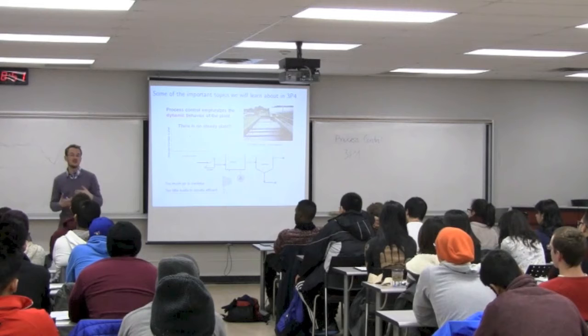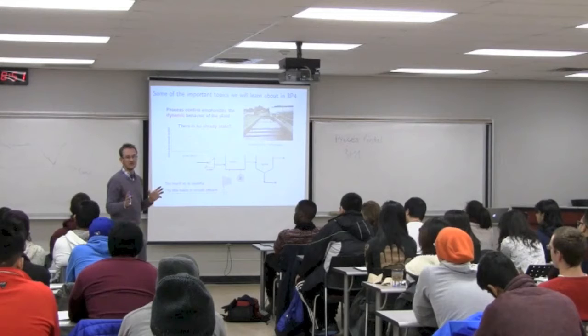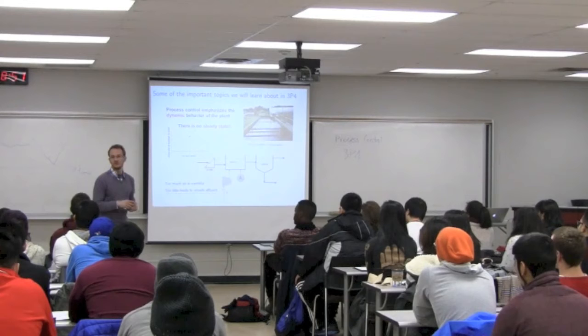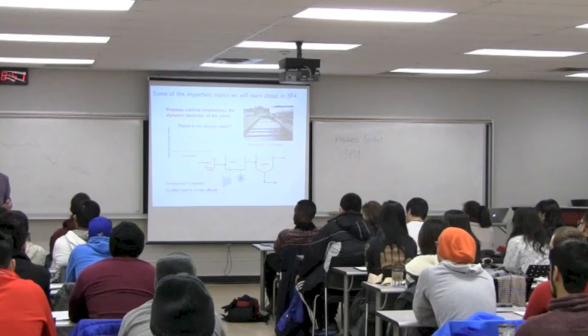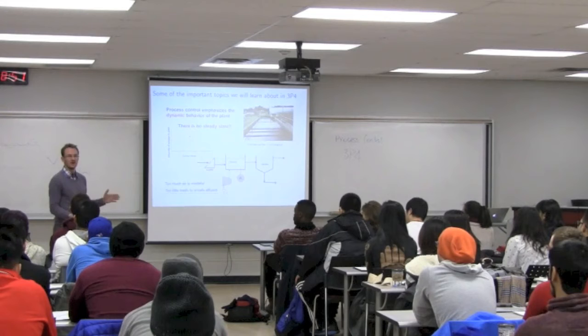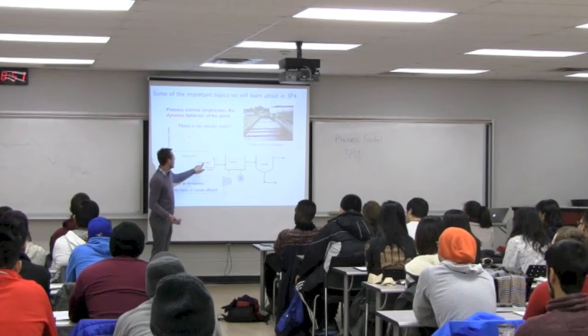Now, obviously, then there's design on how big that vessel should be. There's some engineering work done to design the capacity for that vessel, and they'll design it for most treatment flows. But then a storm comes, and you get a high volume of wastewater coming in because our sewer systems are not separated. Wastewater and water overflow from the roads and snow melting often get combined. So when you get a big ice melt or a big rainstorm, there's this huge flow that comes in, and then this vessel up front doesn't have the capacity. So then you open this valve and you send a higher flow rate to the rest of the process.